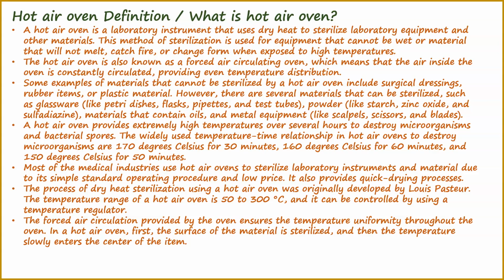A hot air oven provides extremely high temperatures over several hours to destroy microorganisms and bacterial spores. The widely used temperature-time relationships in hot air ovens to destroy microorganisms are 170 degrees Celsius for 30 minutes, 160 degrees Celsius for 60 minutes, and 150 degrees Celsius for 150 minutes.